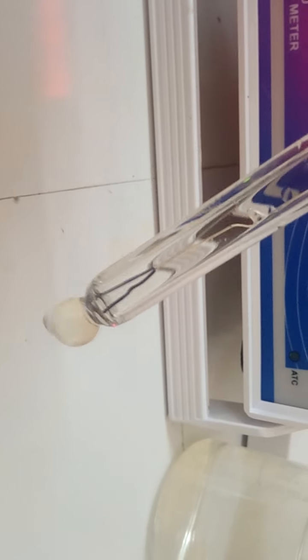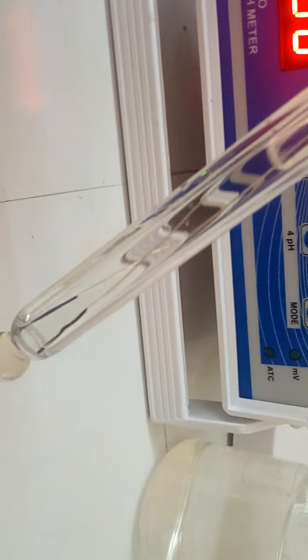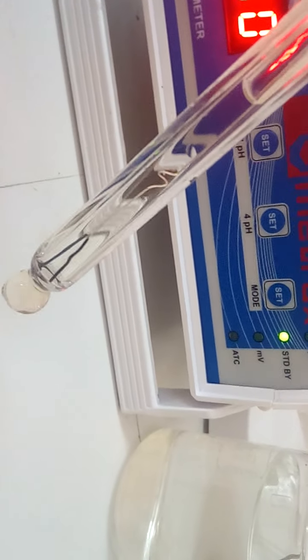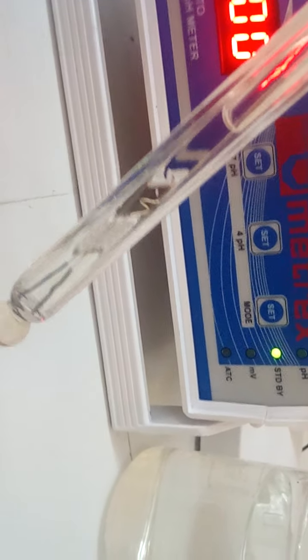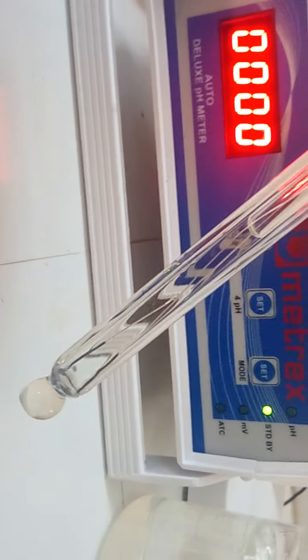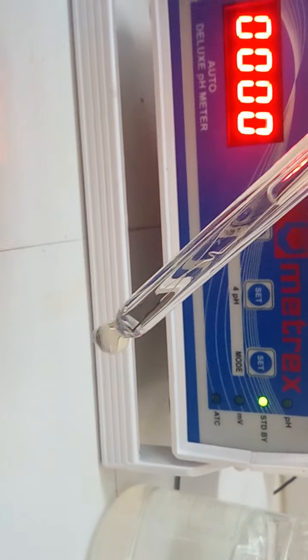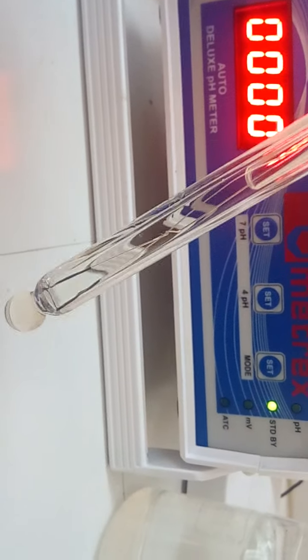In the glass electrode, we can see the Ag wire. This is the reference electrode, filled with KCl solution. Why is KCl solution used? To maintain a constant potential of the AgCl electrode, an electrolyte solution is needed which has sufficient chloride ions and whose pH is neutral. So 3M KCl is used in the glass electrode.